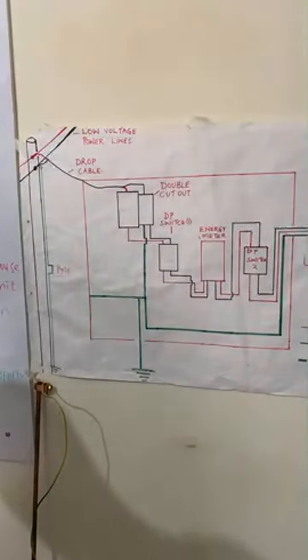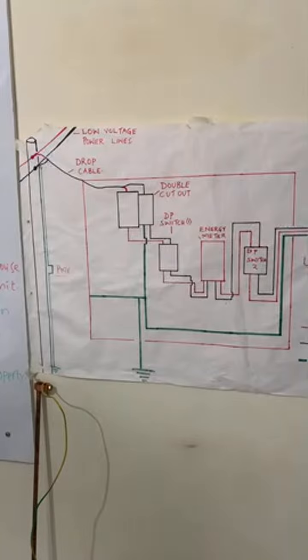Well connected to the earthing system. Anzane says, got a question, top boss. When you connect the neutral and earth cable when dealing with token meters, it will give you a bypass error. Why? Great question. Let us tackle it right there and right then.